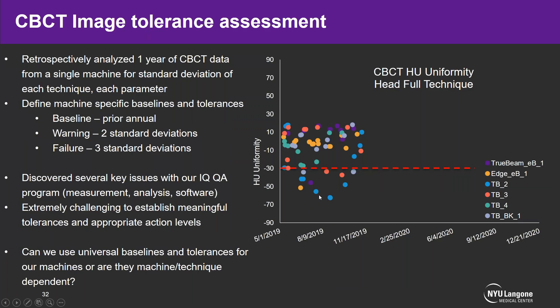After going through all the data, we completely redid our QA program — retraining everyone on acquisition processes to ensure standardization, and making sure analysis software was consistent in SNC Routine. Once we did that, we started to see improvements across all our QA. We had previously been measuring the four most common CBCT techniques every month because we had seen instances where one technique would fall out; we now QA our most common ones on alternating months.